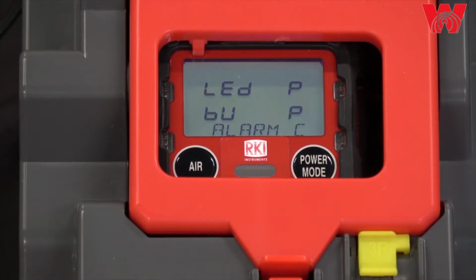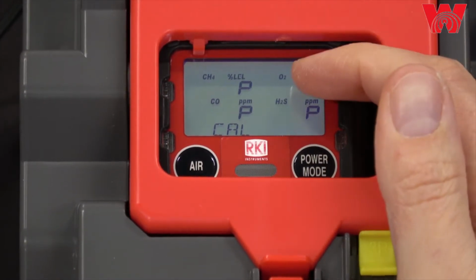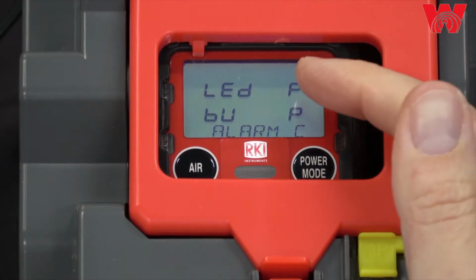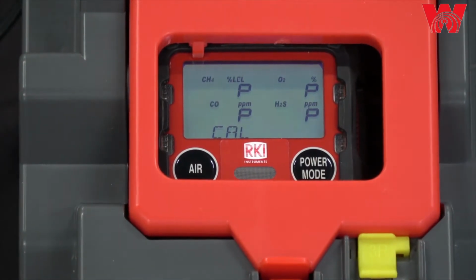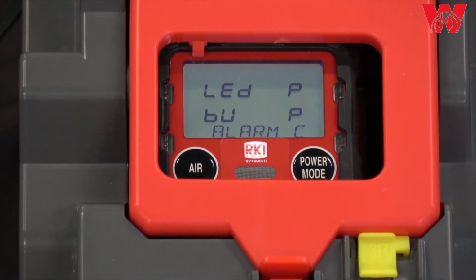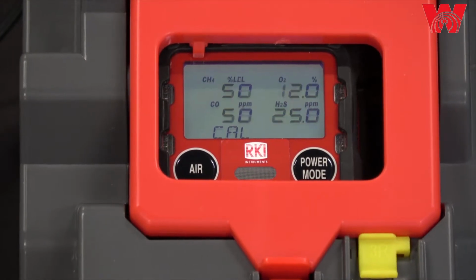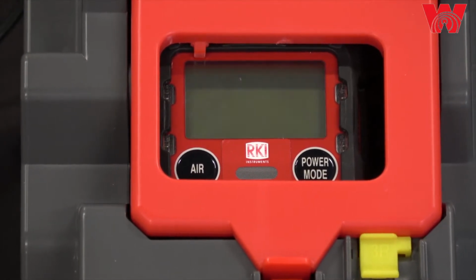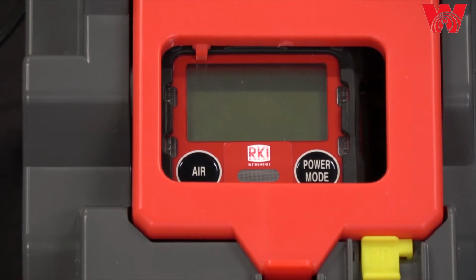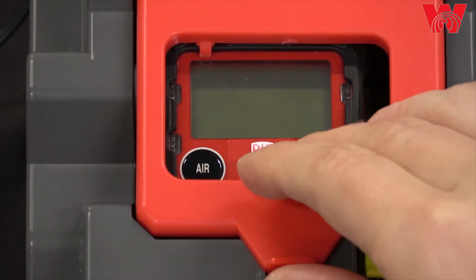So here's the results screen. You can see the calibration result, the calibration readings, and the LED buzzer result. Since everything passed, the instrument is going to turn off automatically, and you can remove it and use it. So now I'm going to show you how to do a bump test using the docking station.